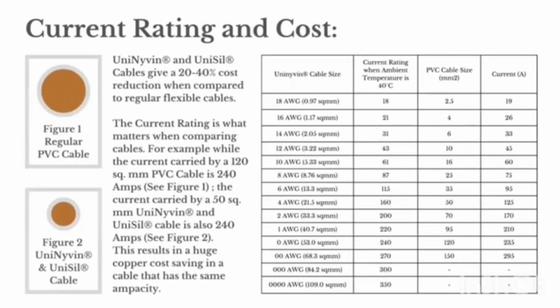Current rating and cost. UniNyvin and UniSil cables give a 20 to 40% cost reduction when compared to regular flexible cables. The current rating is what matters when comparing cables. For example, while the current carried by a 120 square mm PVC cable is 240 amps, the current carried by a 50 square mm UniNyvin and UniSil cable is also 240 amps. This results in a huge copper cost saving in a cable that has the same ampacity.